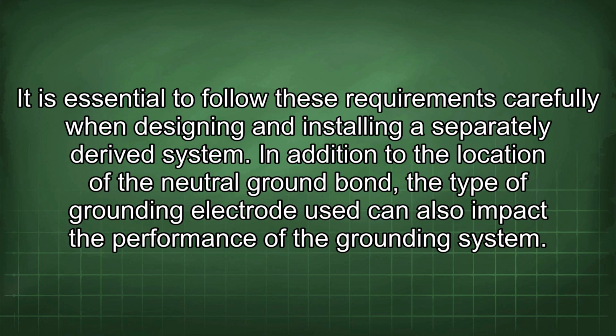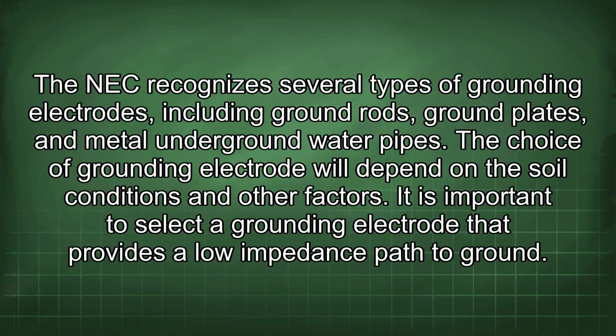In addition to the location of the neutral ground bond, the type of grounding electrode used can also impact the performance of the grounding system. The NEC recognizes several types of grounding electrodes, including ground rods, ground plates, and metal underground water pipes. The choice of grounding electrode will depend on the soil conditions and other factors. It is important to select a grounding electrode that provides a low impedance path to ground.